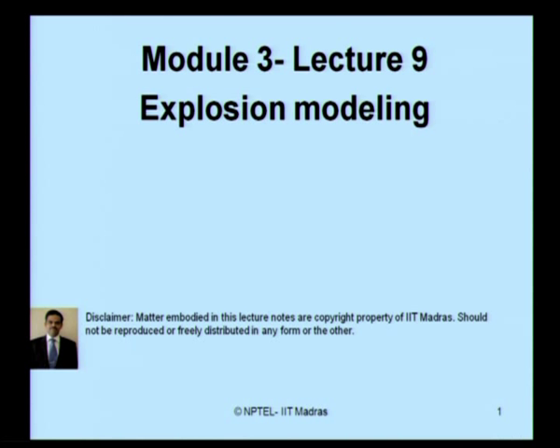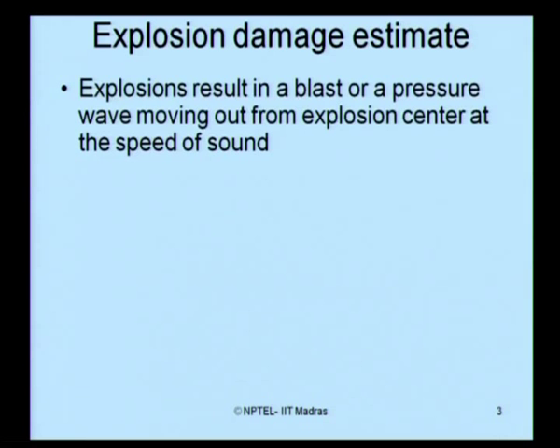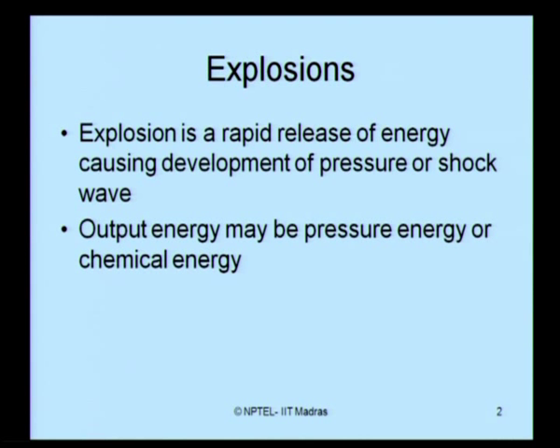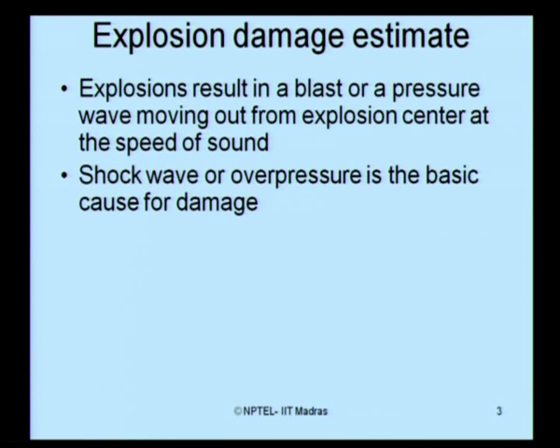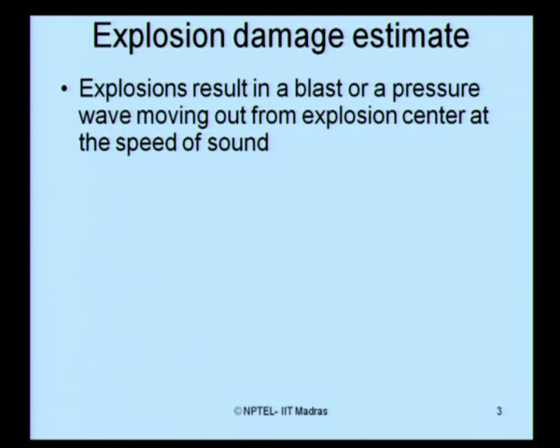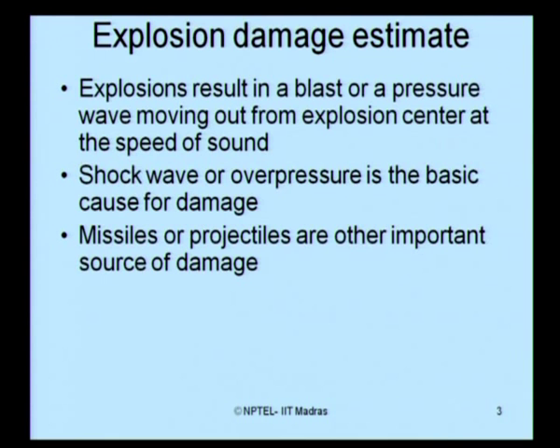Before we discuss different modeling techniques for explosions, let us understand what an explosion is. An explosion is a rapid release of energy causing development of pressure or shock wave. The output energy may be pressure energy or chemical energy. If we want to estimate explosion damages, we must understand that the explosion results in a blast or pressure wave moving out from an explosion center at the speed of sound. The shock wave or overpressure is the basic cause for damage resulting from an explosion. Missiles or projectiles are other important sources of damage. Damage is expressed as a function of rate of pressure increase and duration of the blast wave.